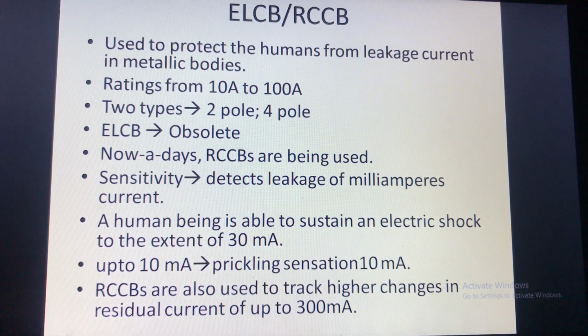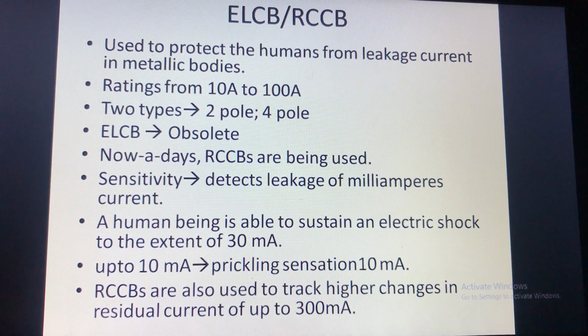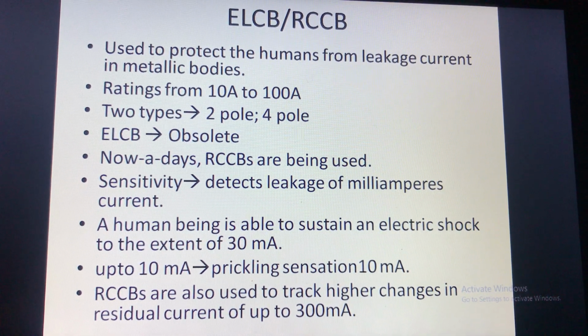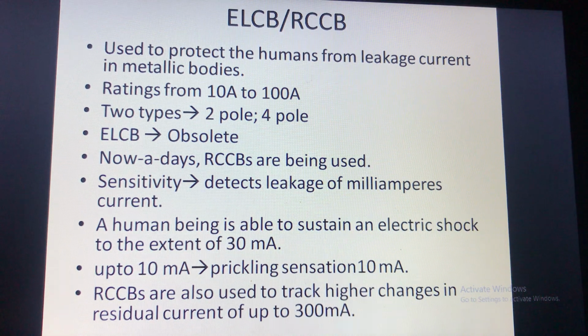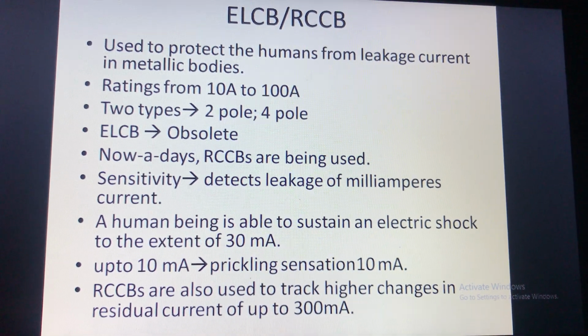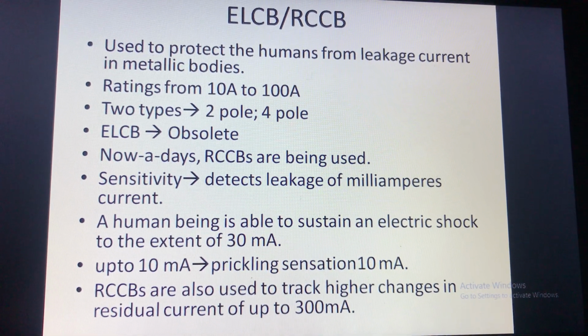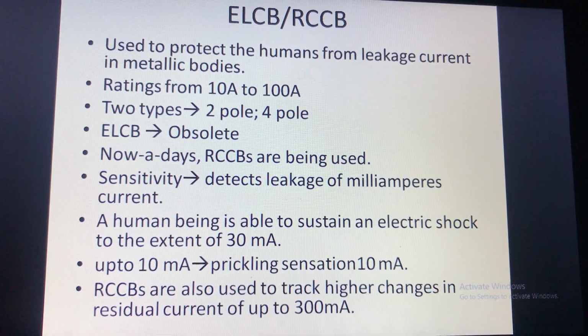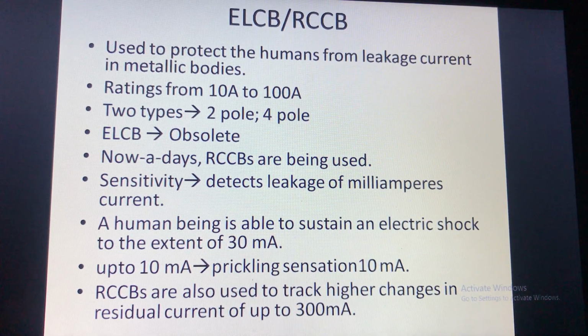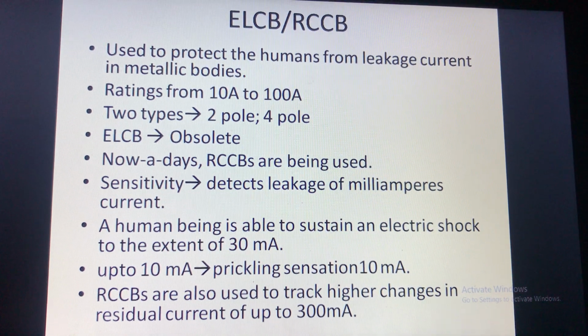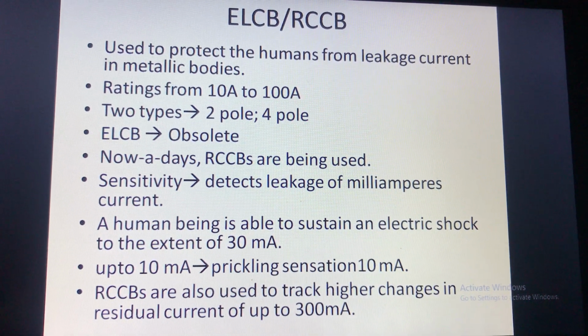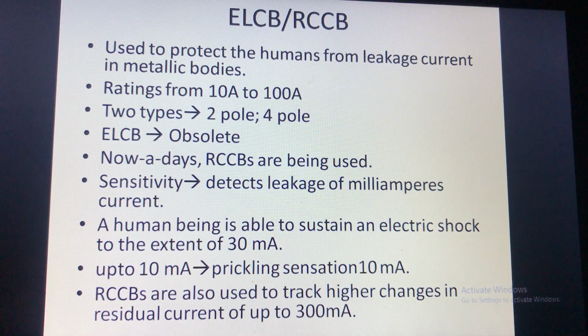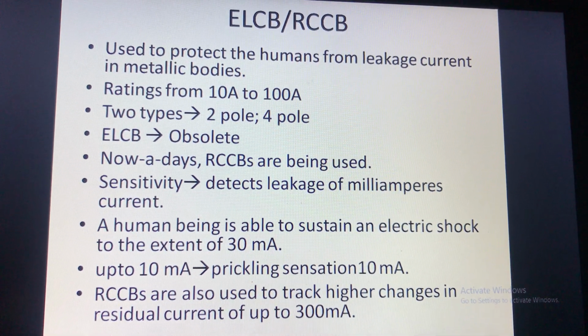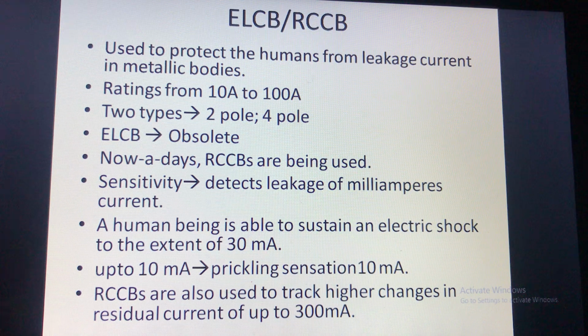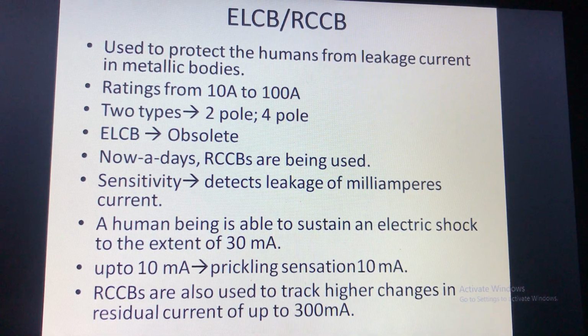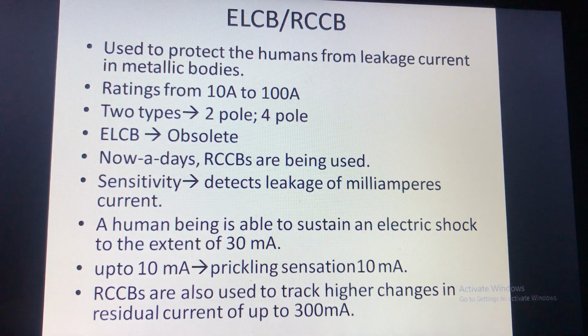ELCB operates on voltage. It is a voltage operated device, whereas RCCB is a current operated device. ELCB measures the voltage in earth wire or ground wire to trip the circuit, whereas RCCB measures the sum of currents in neutral and phase wires to trip the circuit. So nowadays the ELCBs are obsolete, they are not in use, only RCCBs are being used. They are used to protect humans from leakage currents.